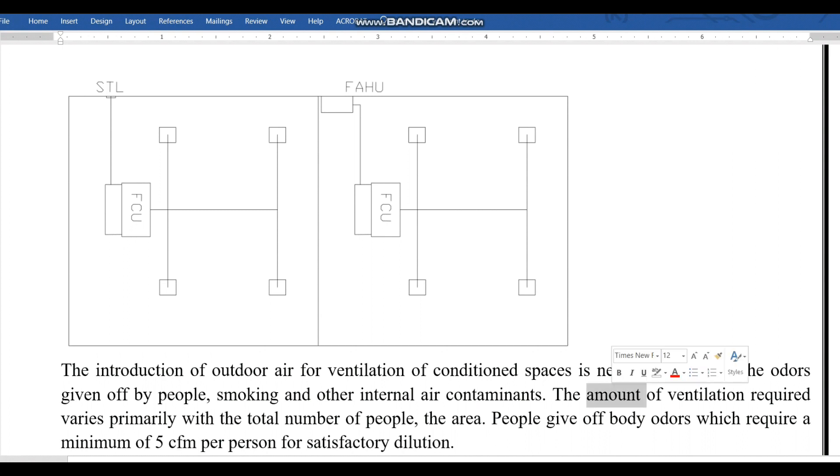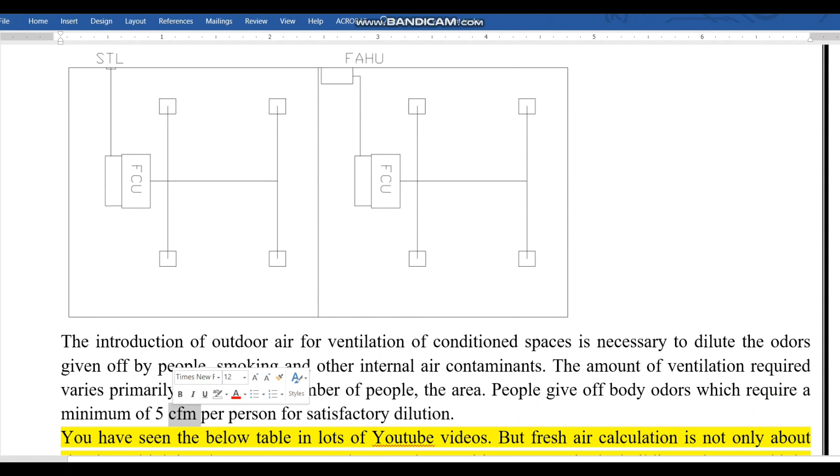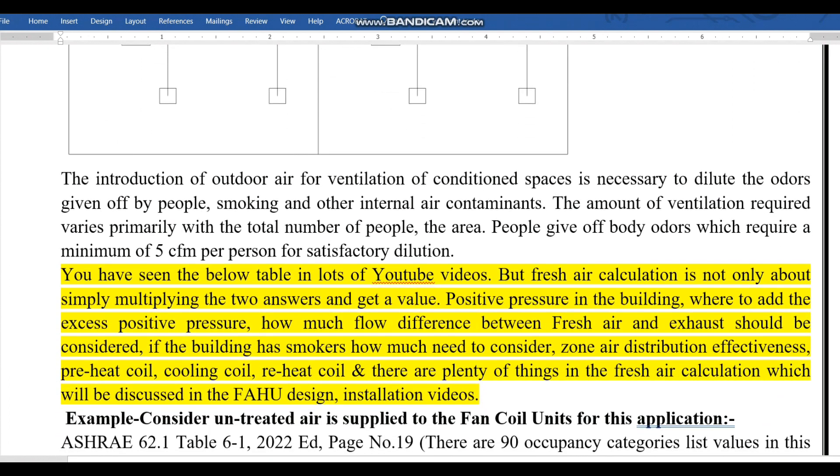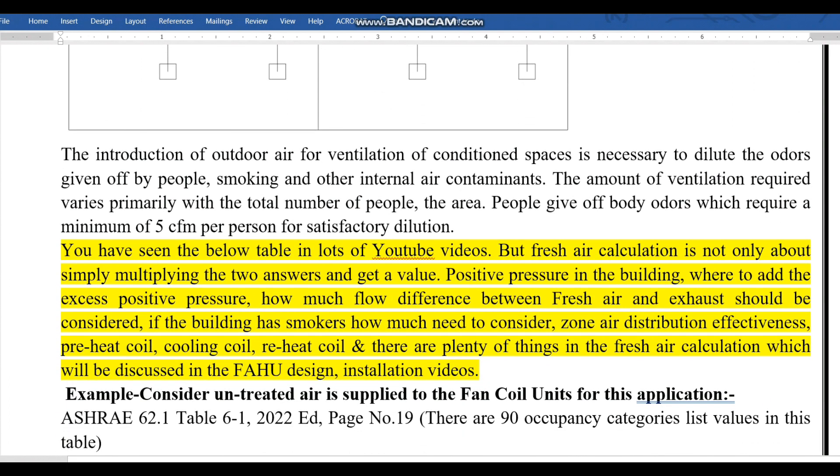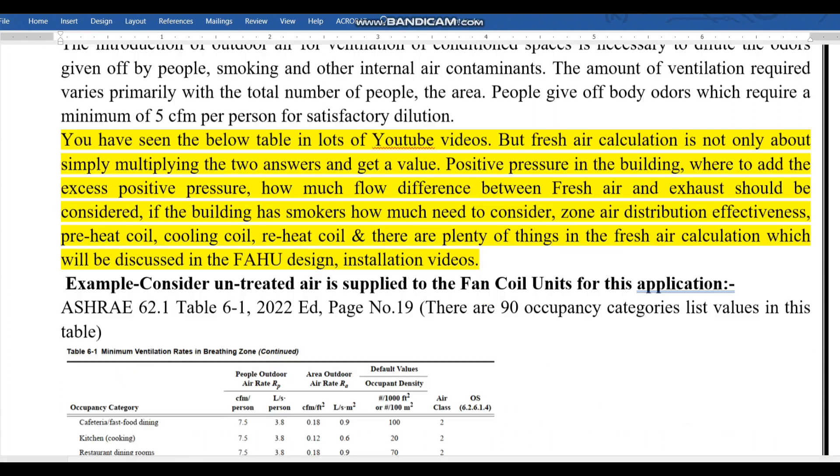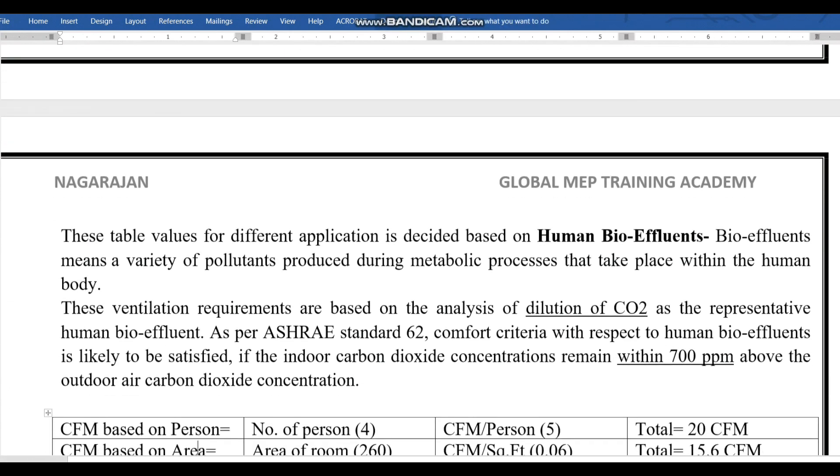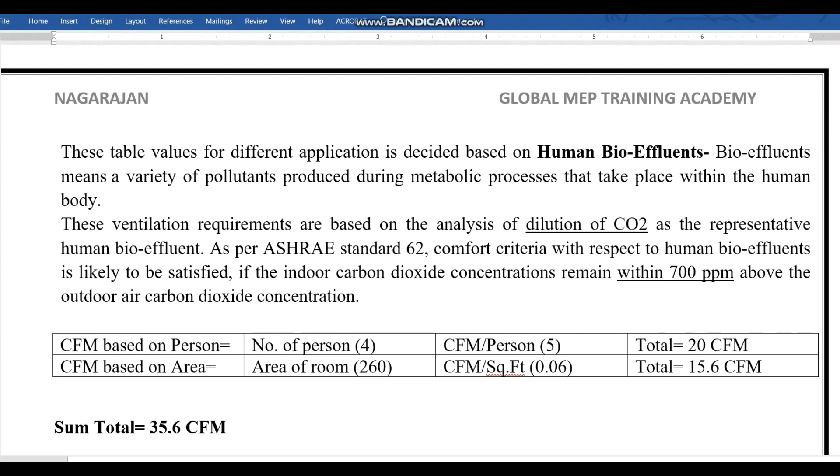The amount of ventilation required varies primarily with the total number of people and the area. People give off body odors which require a minimum of 5 CFM per person for satisfactory dilution. You have seen the table in lots of YouTube videos, but fresh air calculation is not only about simply multiplying.